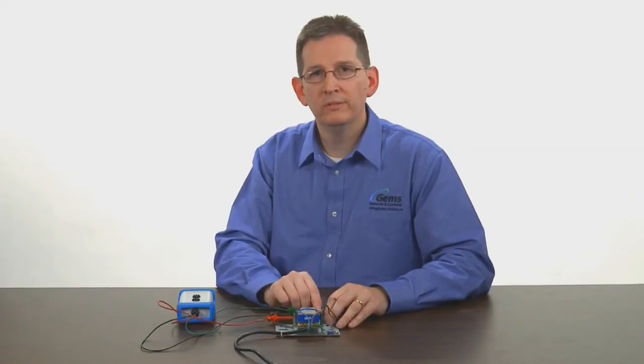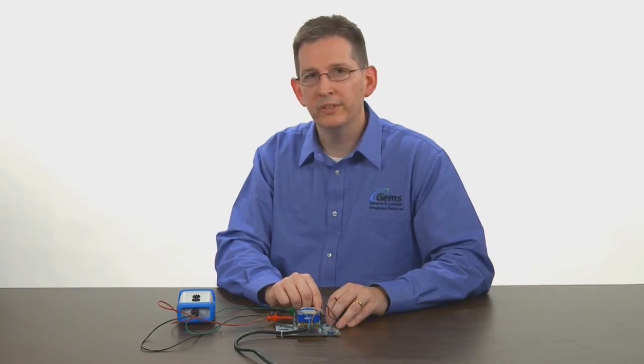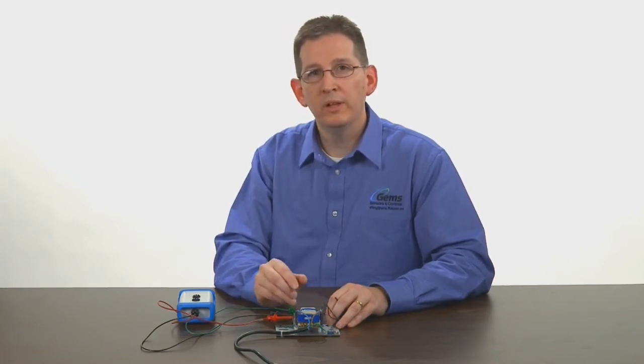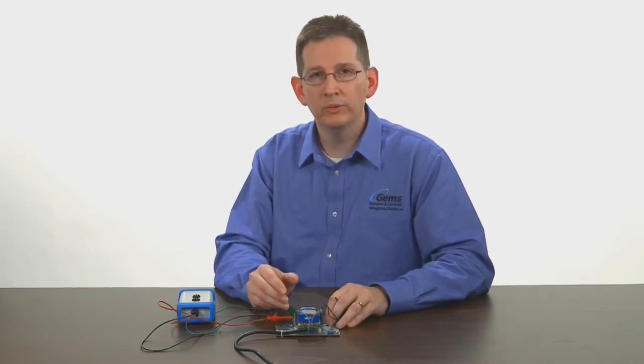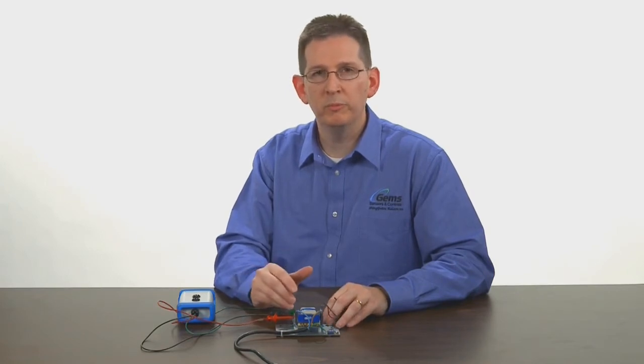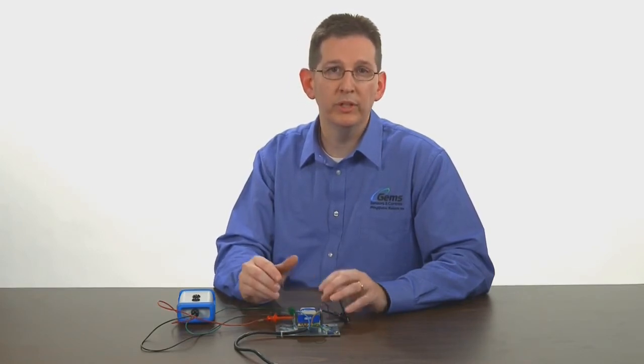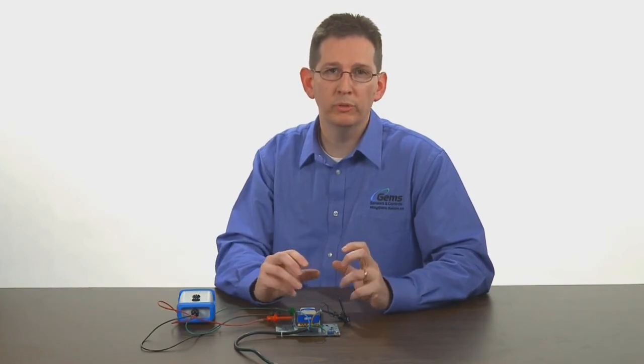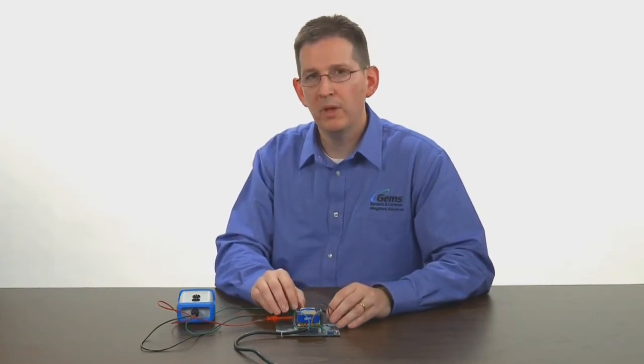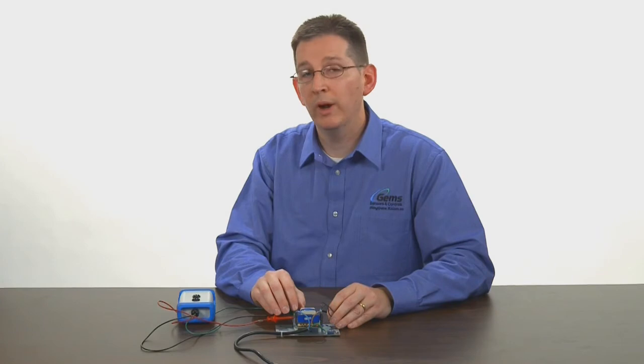Once you've checked your relay for proper functionality a few other things to consider. The cleanliness of your probes is there any buildup of material on those causing a case called bridging material between two probes or to the reference point. Also verify that you've wired your probes correctly and that you have nice tight seals and continuity in your wiring.